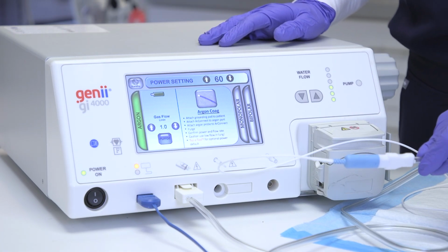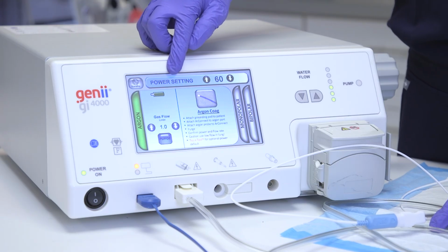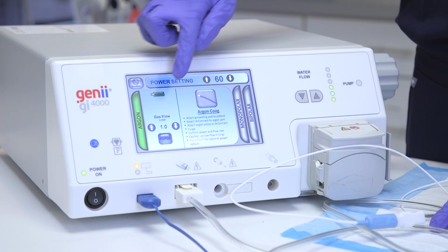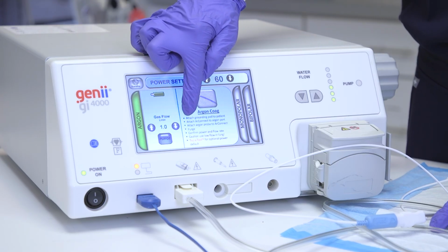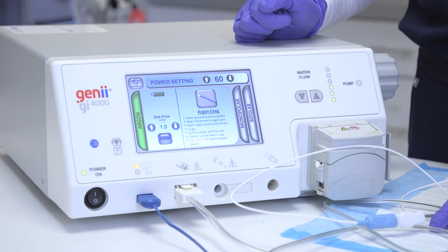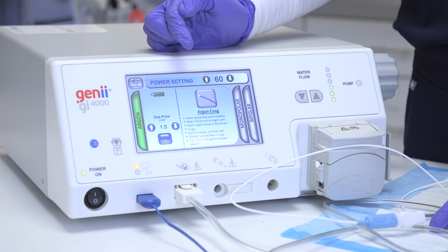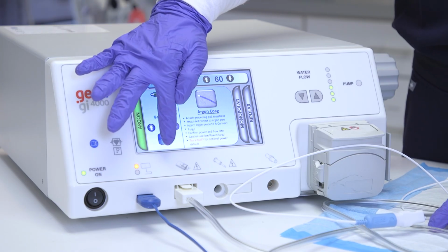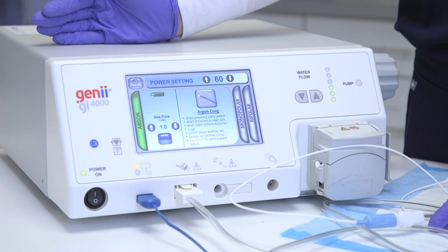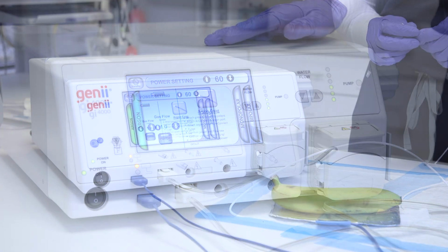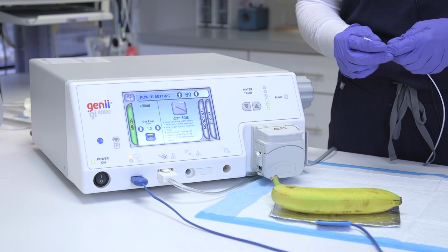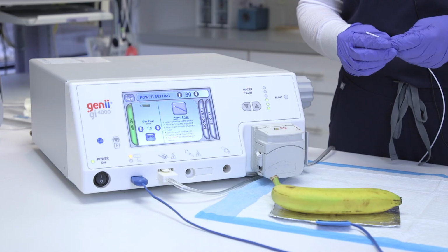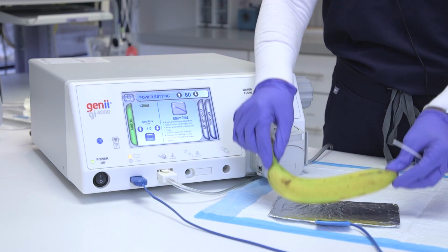After the Argon probe is connected, you'll confirm the default power setting of 60, the gas flow rate of 1.0, and you'll also purge 3 times. Once out of the scope, once after you're through the scope, and a 3rd time in the GI tract. That's how quick the purge sounds. Ideally, you'll want to use a piece of meat on your grounding pad to mimic the mucosa. In a pinch, you can use a banana.